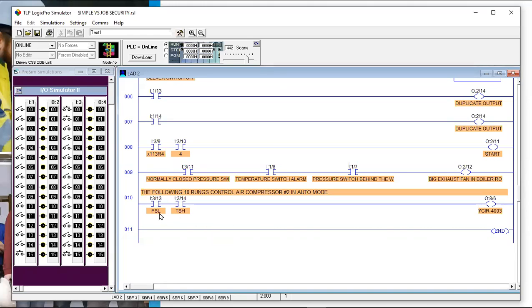Talking about short but not cryptic: we do have standards. For example, PSL is a standard designation for 'pressure switch low', and TSH for 'temperature switch high.' These are standard designations used on P&IDs, schematics, and programs.